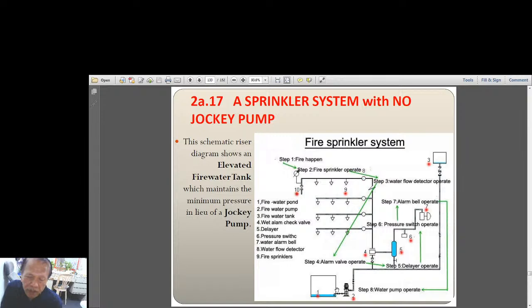Usually you have a fire pump and a jockey pump. Like I said, the jockey pump is the one that maintains pressure in the entire building. But in this illustration, there is no jockey pump. The pressure on the last sprinkler is provided by this elevated tank. This one. Not a very big tank. It's just enough to maintain the pressure on this last sprinkler. Okay. So, is this acceptable? Yes. Because it maintains the pressure in here.